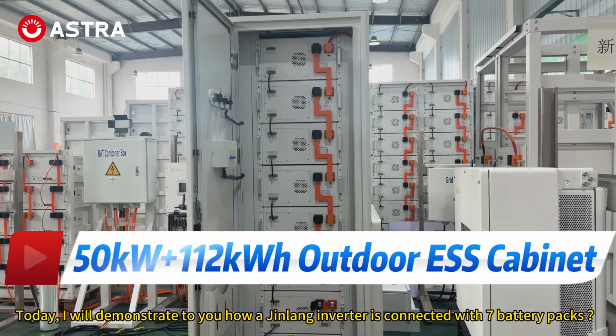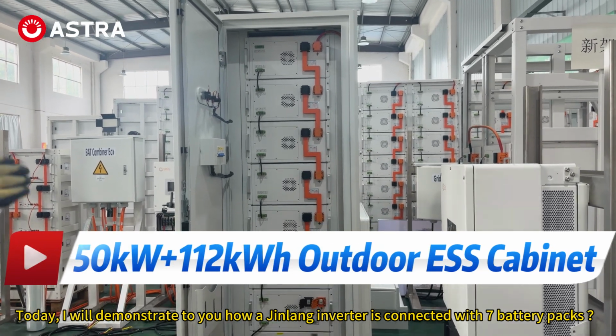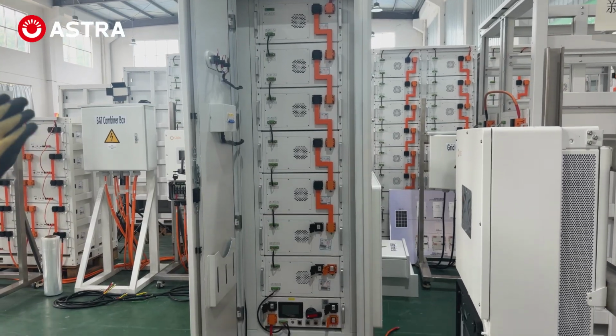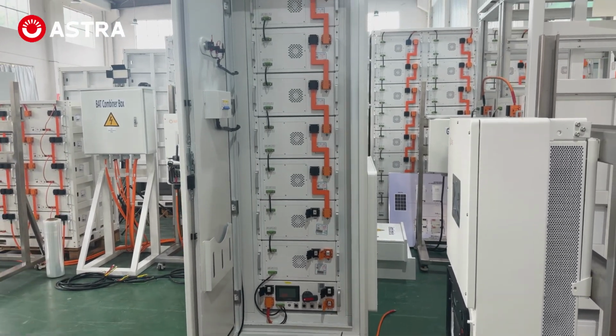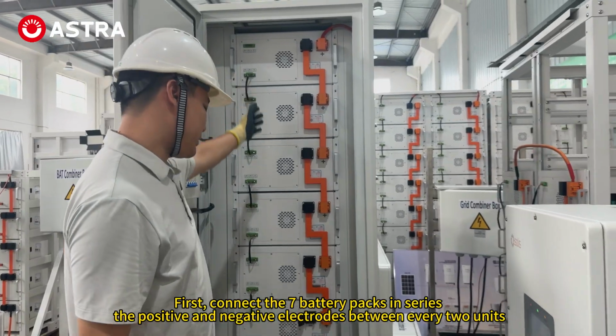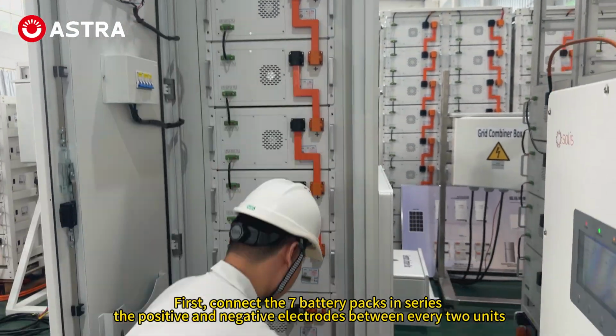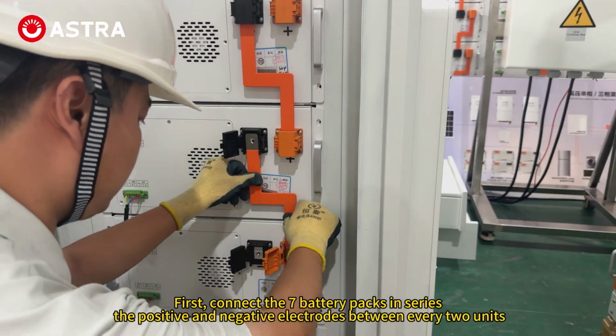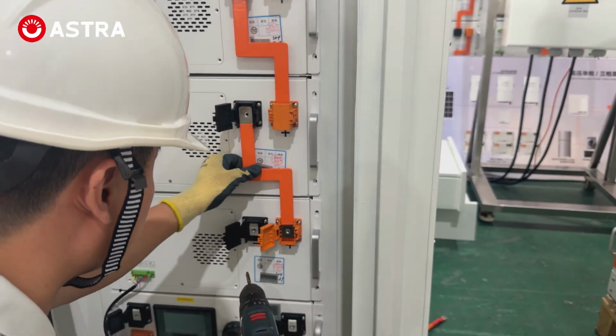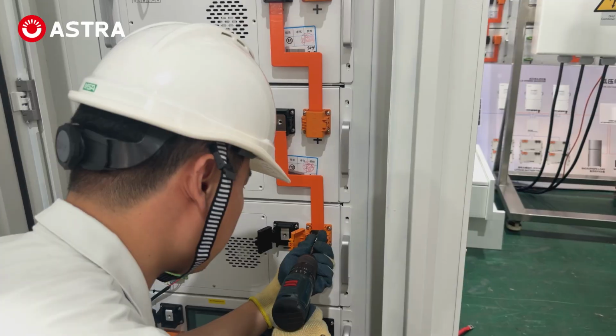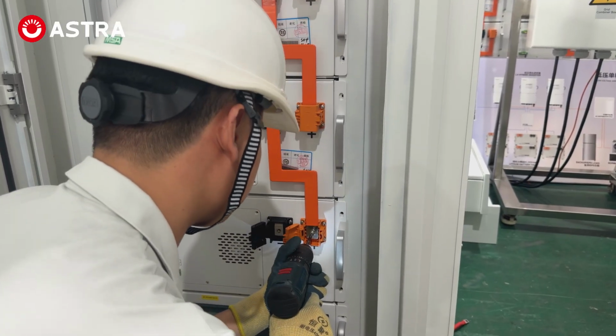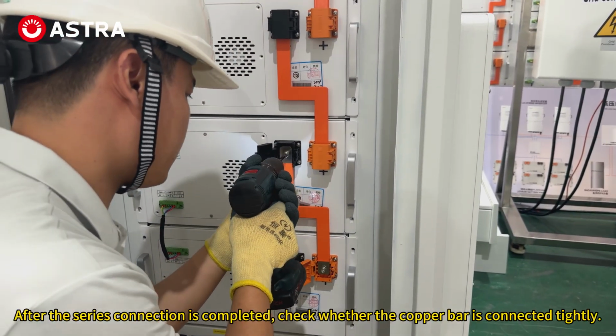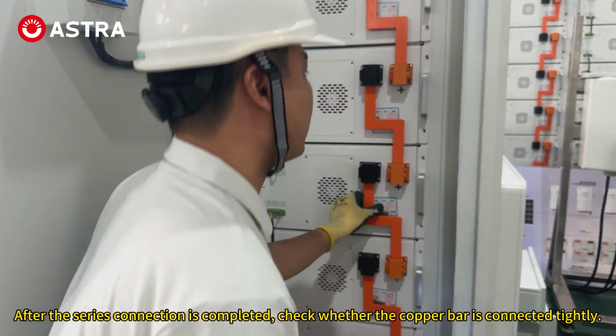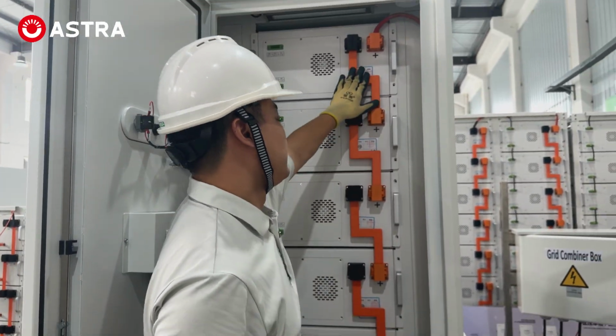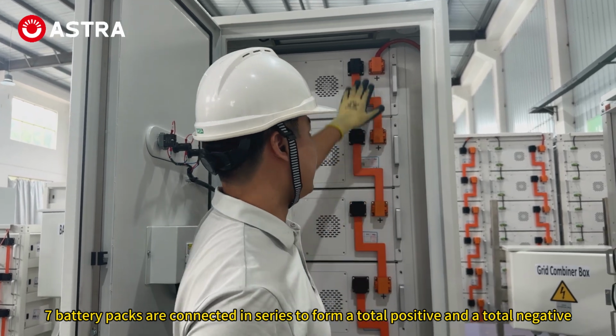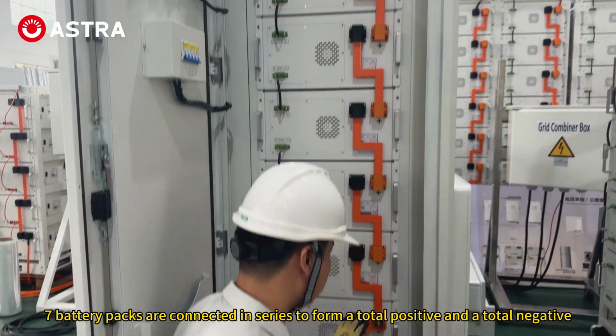Today, I will demonstrate to you how a Jinlang inverter is connected with 7 battery packs. First, connect the 7 battery packs in series, the positive and negative electrodes between every 2 units. After the series connection is completed, check whether the copper bar is connected tightly. 7 battery packs are connected in series to form a total positive and a total negative.